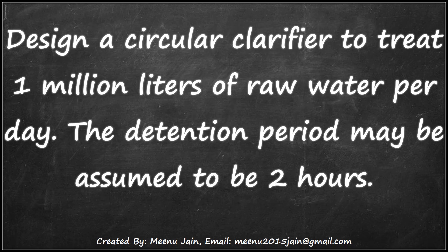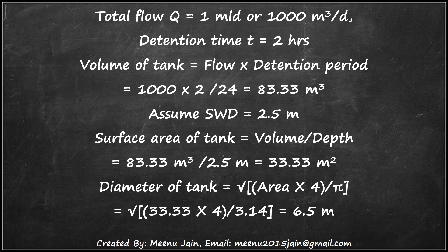Next example: Design a circular clarifier to treat 1 million liters of raw water per day. The detention period may be assumed to be 2 hours. So total flow Q is 1 million liters per day, or 1000 cubic meters per day, and detention time T is 2 hours.